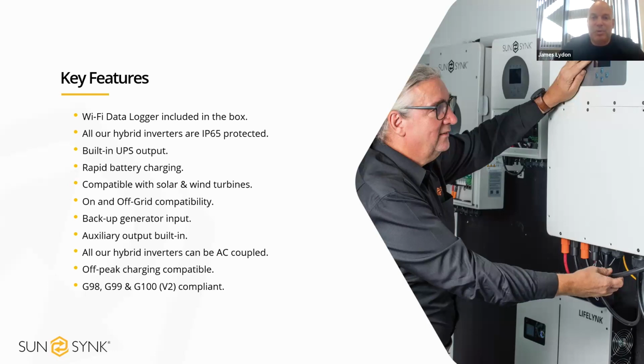All of our inverters can be AC coupled. So whether it's a 3.6 kilowatt hybrid inverter or a 50 kilowatt three-phase hybrid inverter, if you've got a customer who's got an existing PV system on their roof, whether it's on the feed-in tariff or on a commercial building, and they're looking at their data and they say, right, we're exporting quite a lot of power here to the grid, you can simply install any of our hybrid inverters with the required amount of battery storage, and our smart CT clamp will see when anything else on that MPAN is exporting. So as soon as we see that export going via our CT, the CT will then instruct our inverter to charge the batteries at the same power. And then obviously, once the house load increases and the current string inverters can't satisfy the load, the batteries will then discharge to supplement it.